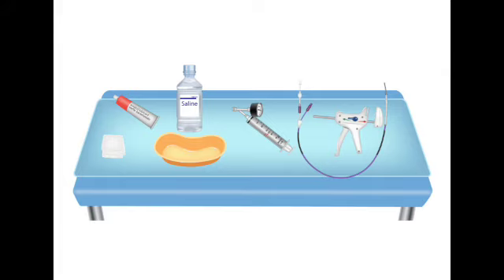So having those sizes on hand is key. But the technology itself is what's really fascinating, especially these controlled radial expansion balloons, the CRE balloons. This is where things get really interesting from an engineering standpoint. You have your basic fixed-size balloons where one inflation gives you one diameter. Simple enough. But the CRE balloons are marvels. A single balloon can achieve several different diameters. For instance, it can go from 6 millimeters up to 9 millimeters in the same session. Just by adjusting the pressure. Just by adjusting the pressure dictates the size. So it's completely dynamic. Right.